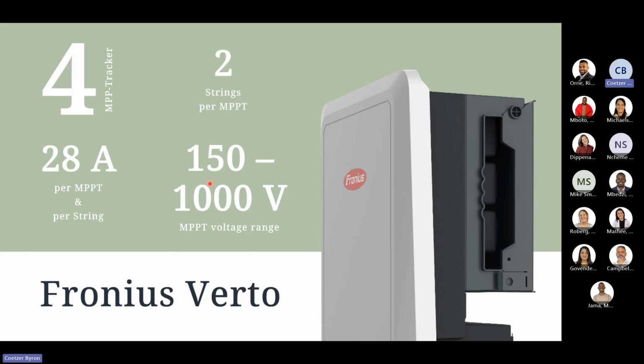What's also handy is we've changed the MPPT voltage range. Instead of being, for example, 580 to 1000, we've now shifted it down to 150 volts, all the way up to 1000 volts, both on the input and usable range. The usable range is from 150 to 870 volts, for example. So you've got a much wider voltage range to use with the Verto instead of the Eco, for example. That's something new and exciting coming from Fronius.